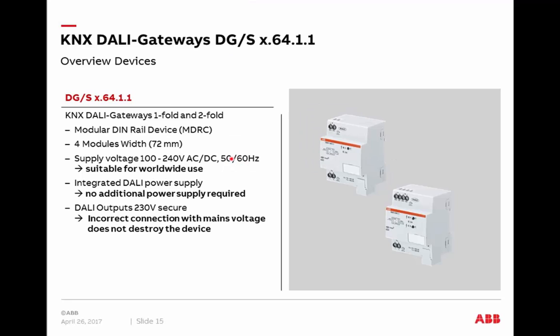Looking at both devices together, they share common general features. The component is a modular DALI device with four module widths. You must connect mains voltage on the lower left side — between 100 and 240 volts AC or DC — making it suitable for worldwide use. There is an integrated DALI power supply. One improvement: the DALI output is now 230-volt secured — if 230 volts is accidentally connected to the low-voltage DALI output, the component will not be destroyed, unlike existing devices. After such a connection, the component can still be used without malfunction.